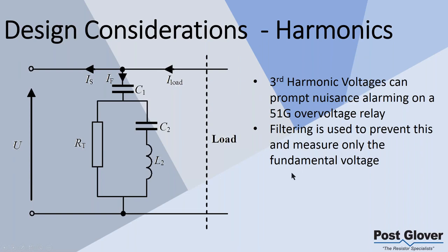So it doesn't matter. Once again, it doesn't matter if you're just ignoring the third harmonics or you're actually actively filtering it out. You need to make sure that there is some way you're doing it. It also doesn't necessarily matter where you do it. You have to do it. As long as you're protecting the controls relays, you can do it separately in the HRG. You can do it on the relay, wherever you can get it from, as long as that relay is not tripping or alarming based off of that third harmonic false current, essentially, because false voltage, because the voltage is going to be fundamental from the system.